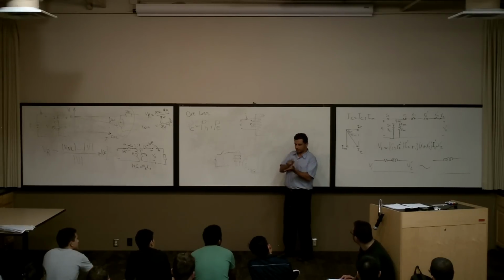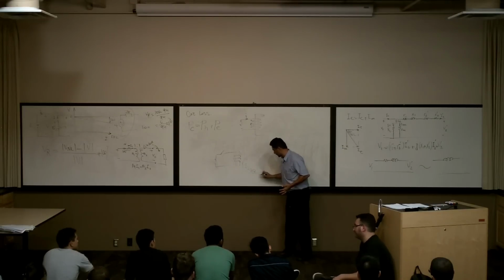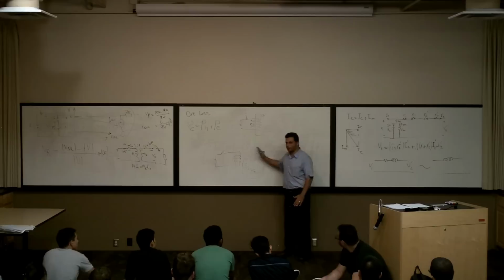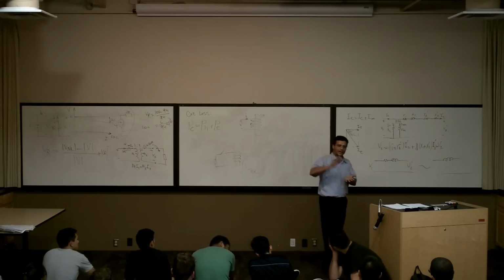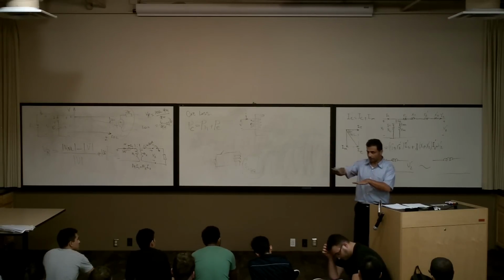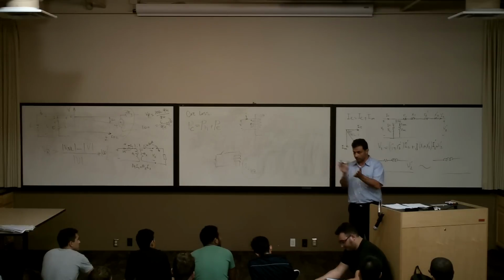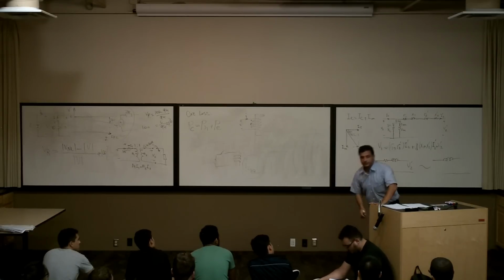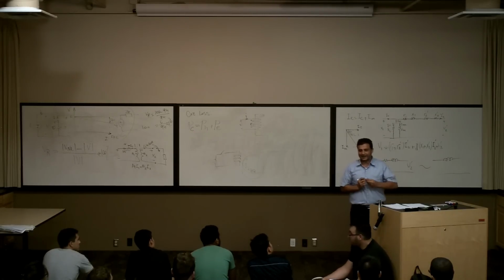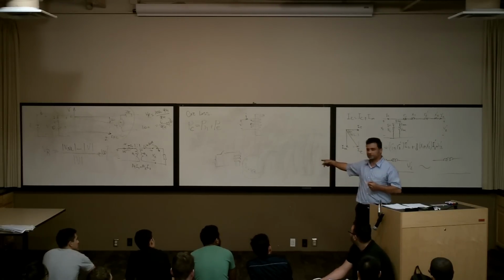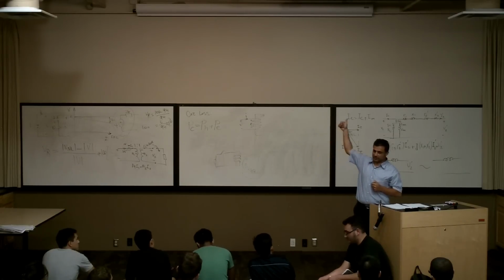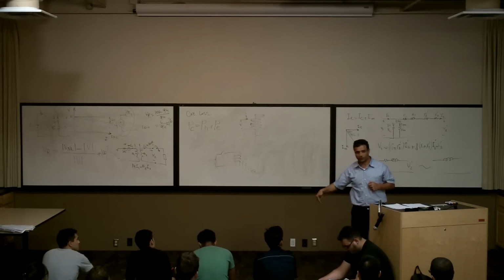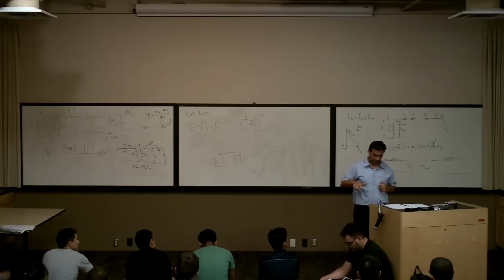You do the lamination. For example, let's say this disk is this much thick. If you make this one, instead of one piece, 10 layers, and you put a kind of insulator between the layers, you cannot put them on top of each other, just put a kind of insulator between the layers. That practically is increasing the resistance of this eddy current path. When the resistance goes up, the current goes down. When the current goes down, the eddy current loss will be reduced.